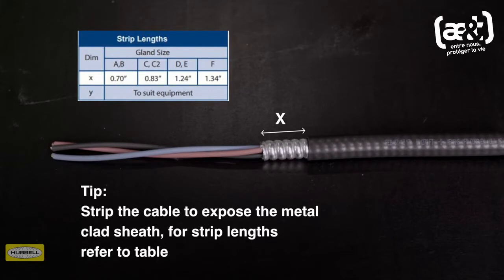Remove a further 0.7 inches of metal clad sheath for cable glands A to B size, 0.83 inches for C to C2 size, 1.24 inches for D to E size, and 1.34 inches for F size.